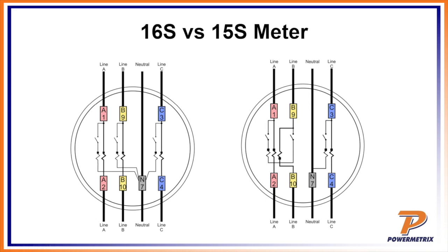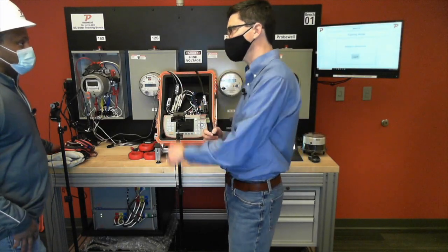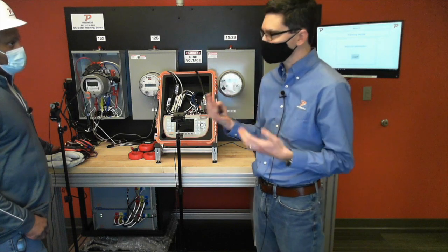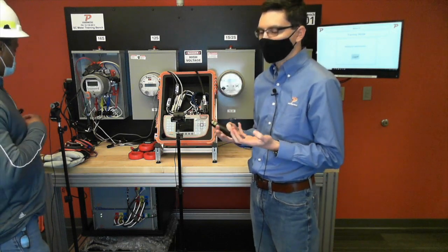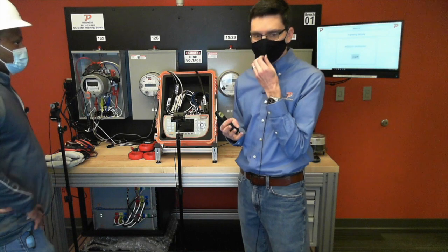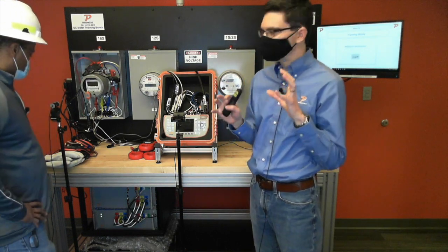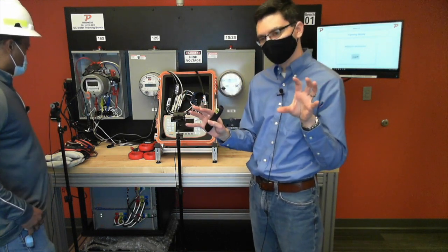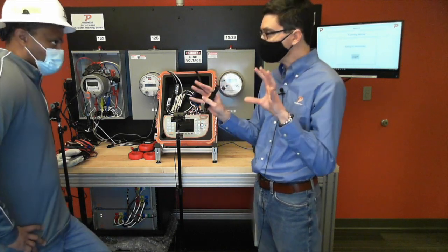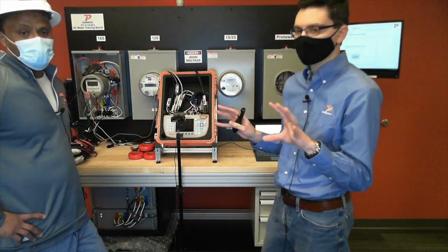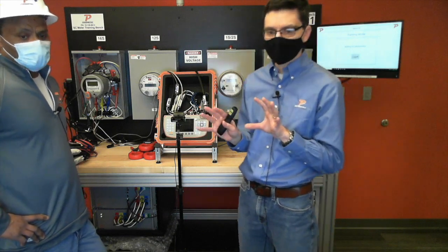GE, or Elster now, came out with a fits-all meter, and I think Elster still has one. On their faceplate they've got a 15S/16S meter, and what they say is it can support both services. But back in the day, probably in the 80s, they had these 15S mechanical meters and 16S mechanical meters that, even though the same socket could support them, metered differently. They also have different voltages.